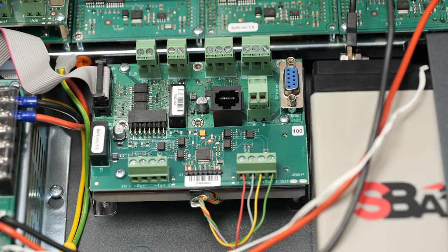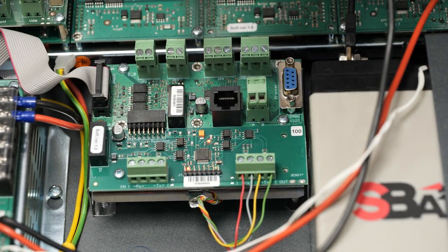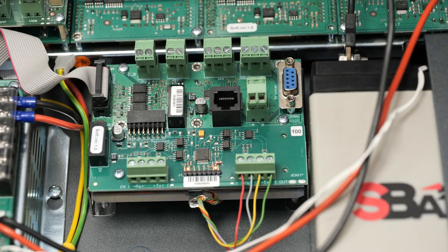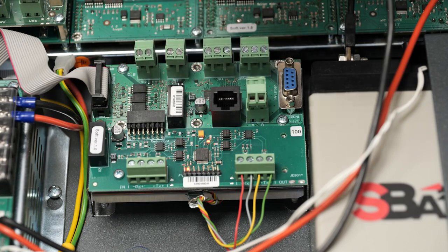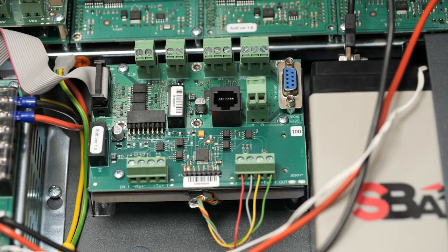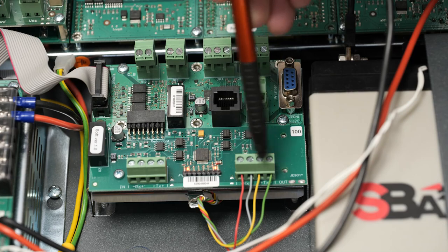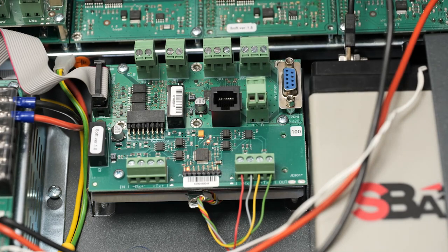The network module is an additional PCB mounted under the main board of the panel, and it is connected to the network connector. In this case, we are using an IRIS panel for the example. The redundant network uses 4 wires for communication between the panels in the network, going from one panel to another panel. We have the in terminal, which we use for connection with the previous panel in the network, and the out terminal, which we use for the next panel in the network or for completing the redundancy of the RS485 network, as you can see on the next diagram.